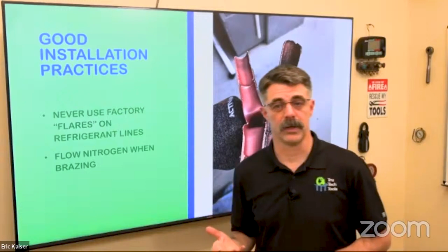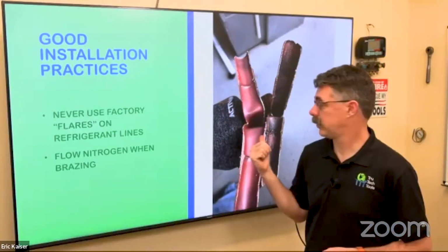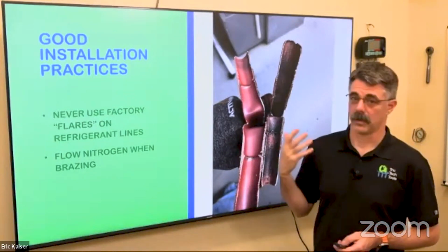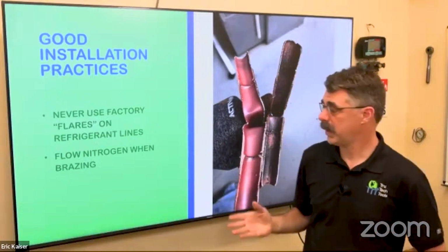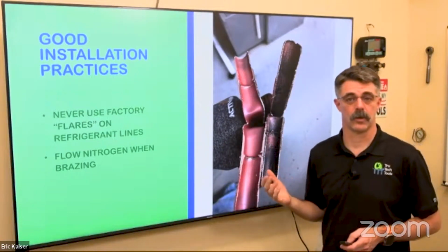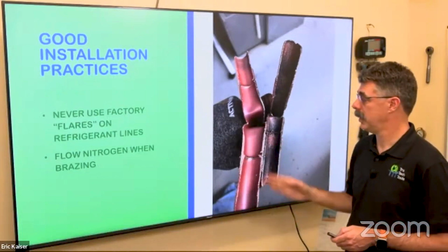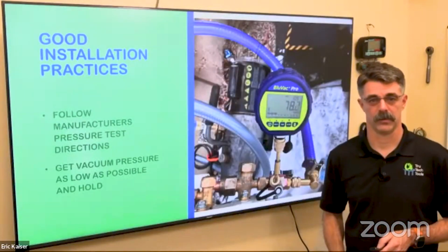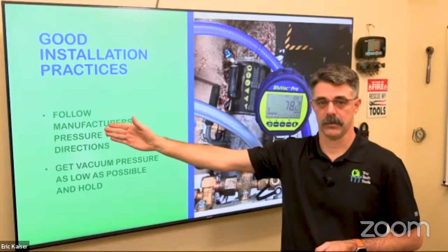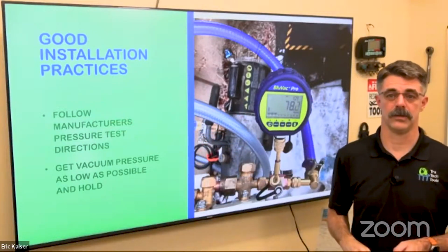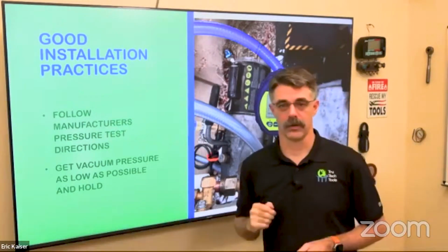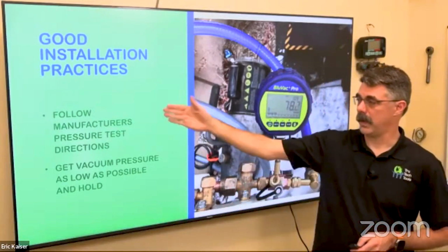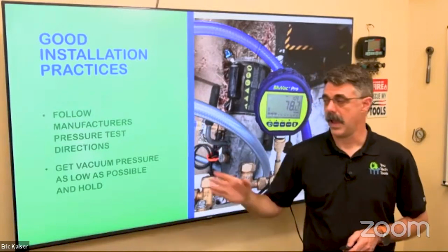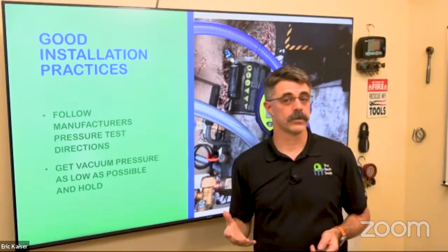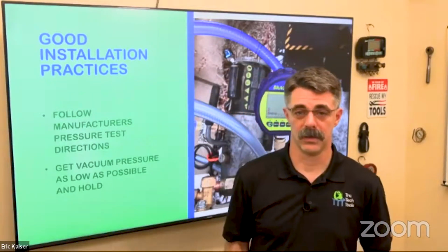Well, the compressor has bearings in it and there's oil in the system. And that means that this is going to wear bearings out, which isn't great. It's going to clog up dryers, may clog up TXVs, can do all kinds of stuff. But it may not happen for a few years. It may take a couple years for that to show up if this is floating around in the system in small amounts. So good idea, best practice: follow good installation practices. Make sure you're following the manufacturer's pressure test directions. In general, follow the manufacturer's installation guidelines, but this is a corner that gets cut a lot, so I'd like to highlight this. Make sure the pressure test is done correctly and get your vacuum as low as possible. The refrigerant system is not easy to repair on a heat pump, so we want to make sure that everything inside that refrigerant system is done correctly the first time.